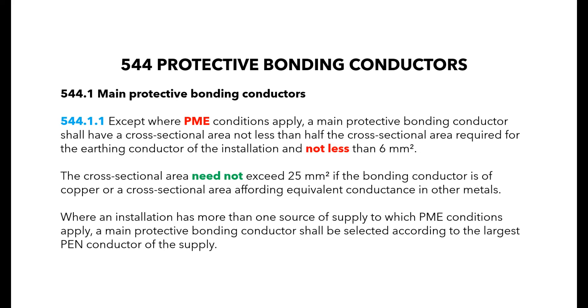Except where PME conditions apply, a main protective bonding conductor should not be less than half the CSA of the earthing conductor and not less than 6mm squared. Although usually in a domestic installation, you will find that a 10mm squared cable will be installed in most situations.